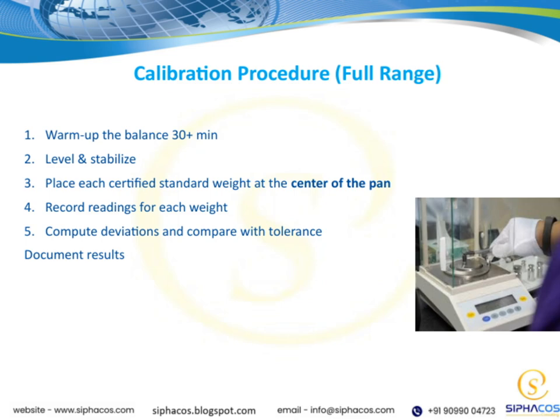If the deviations are within tolerance, the balance is considered calibrated. If not, adjustments or maintenance may be necessary. Finally, document all the results thoroughly. Keeping detailed records of each calibration step and outcome is vital for quality assurance and traceability. Remember, a well-documented calibration not only confirms the accuracy of your instrument, but also supports compliance with quality standards. This process ensures the balance provides reliable measurements, which is the backbone of maintaining overall measurement integrity in our work.